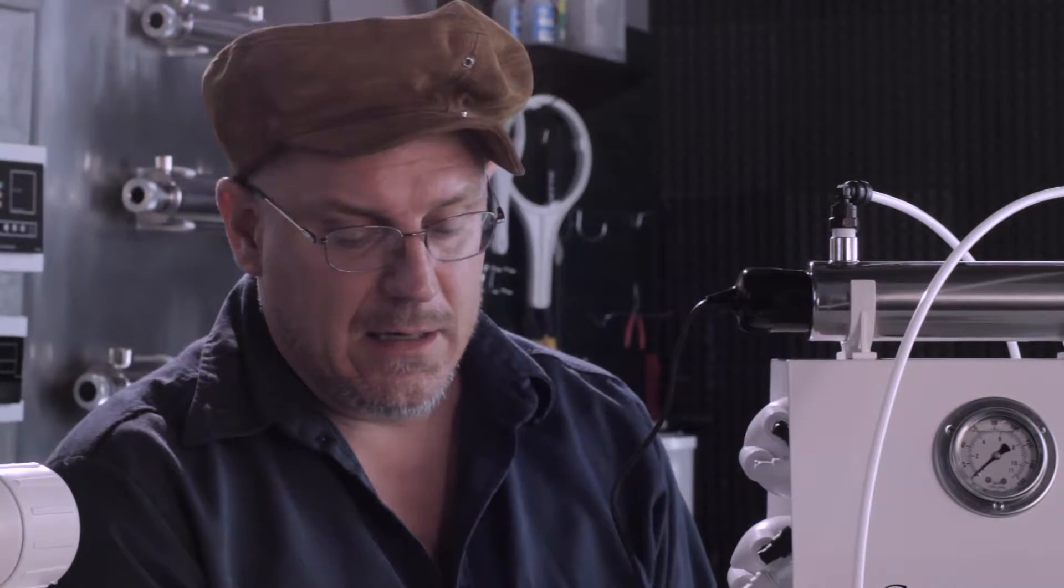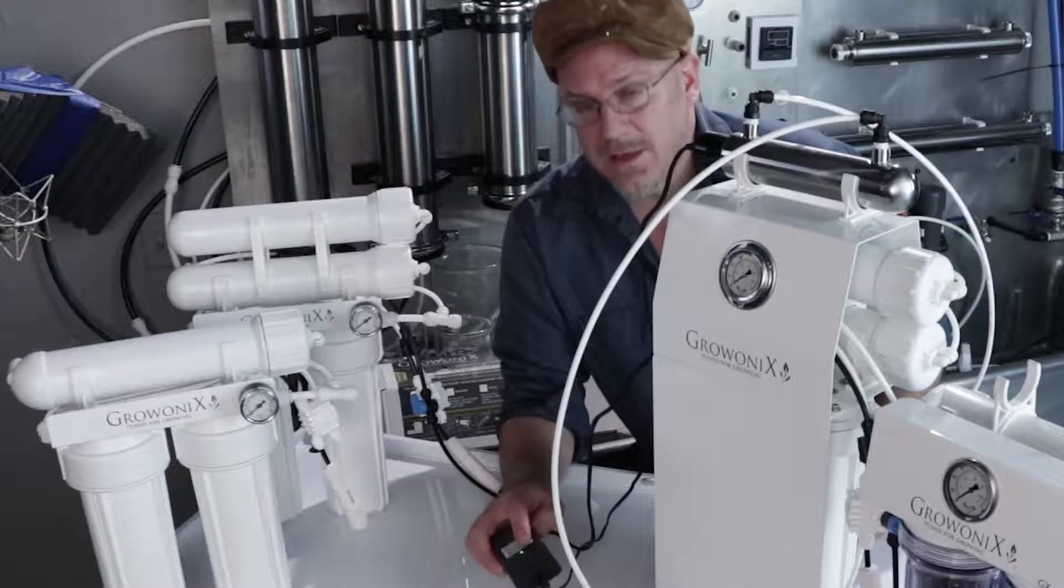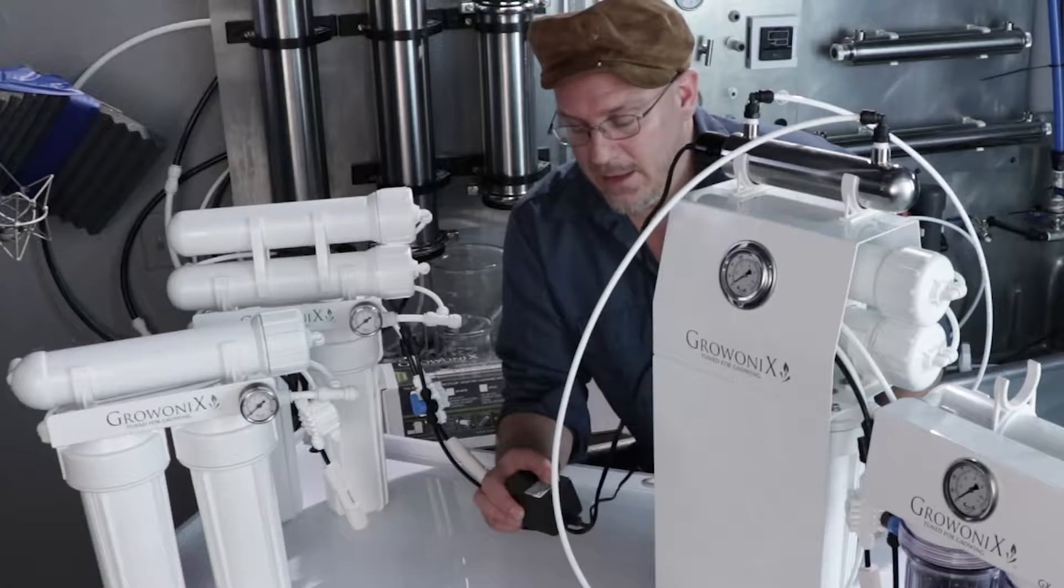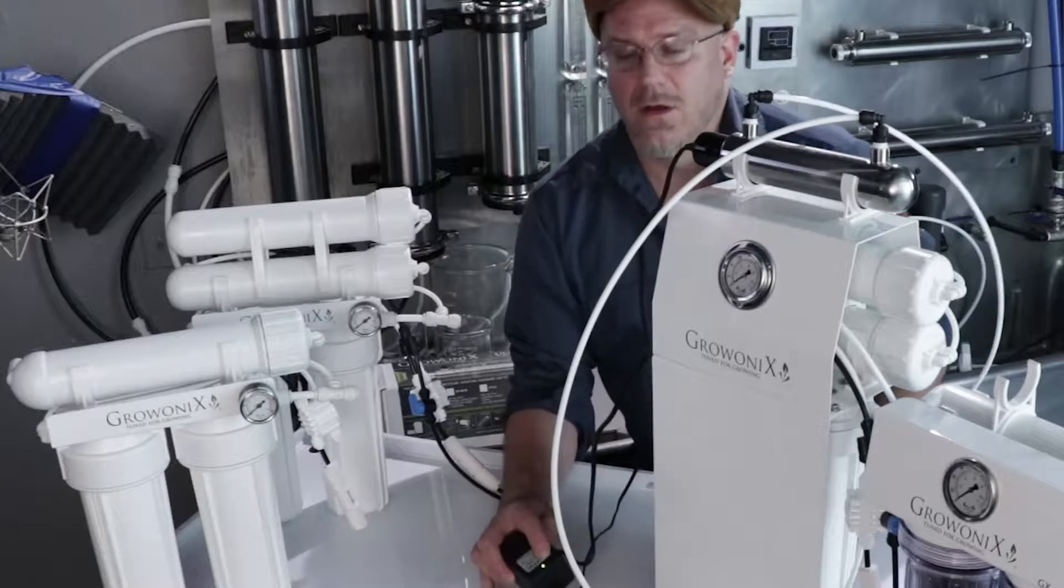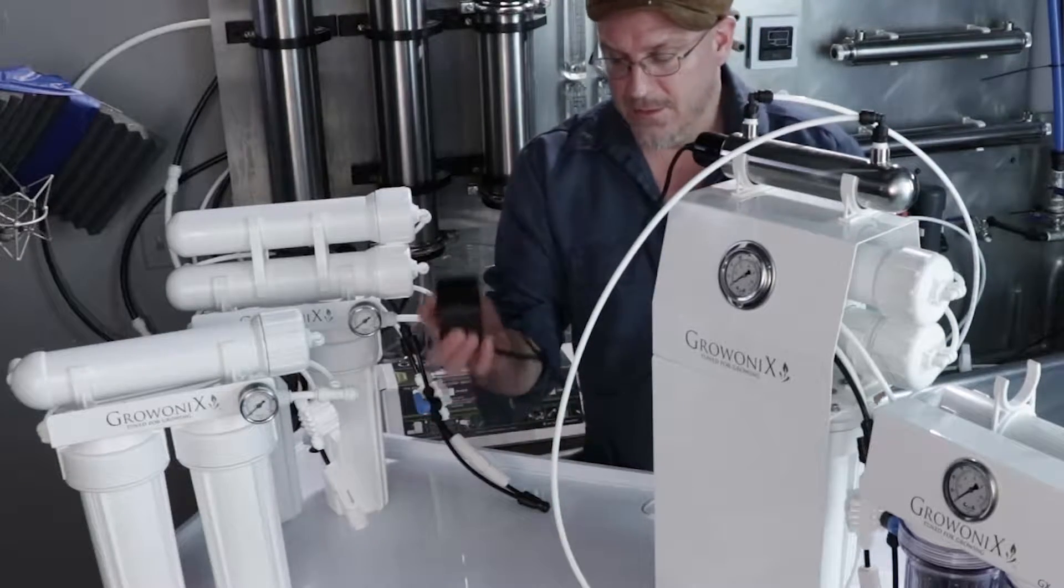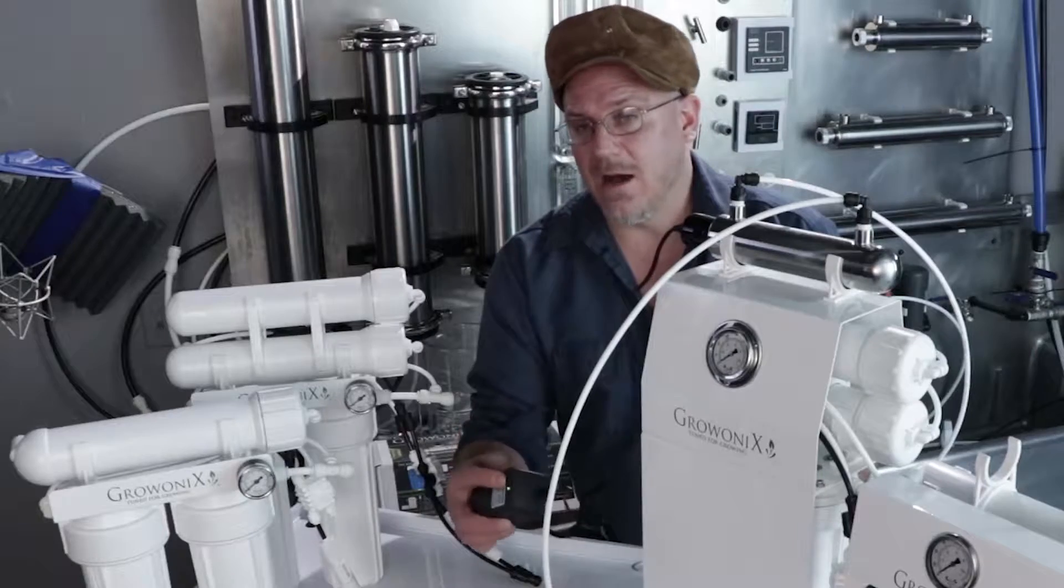To know that it's working, you'll know that the light on here is green. Now, if this light is not green and illuminated, that means the bulb is burned out, or there's no power to the transformer itself. But if the transformer is plugged into 120 volt mains, and this bulb is out, that means the bulb in the UV needs to be replaced.